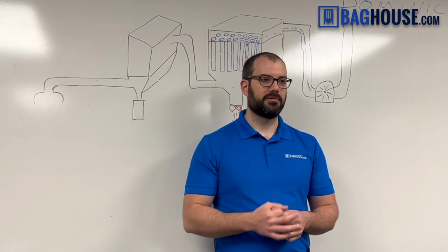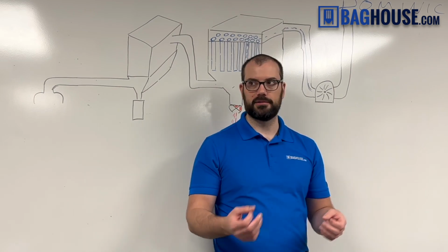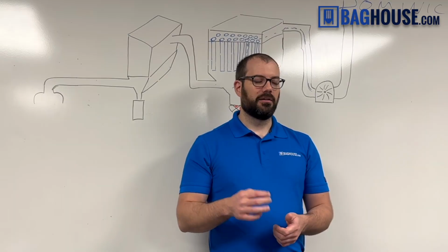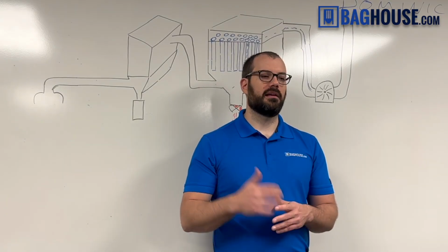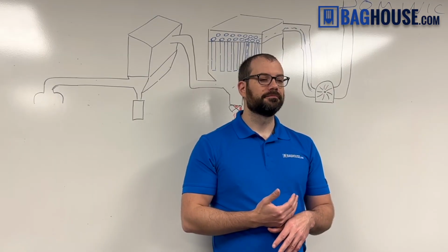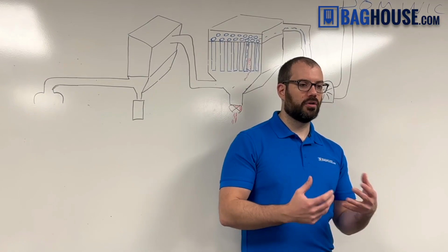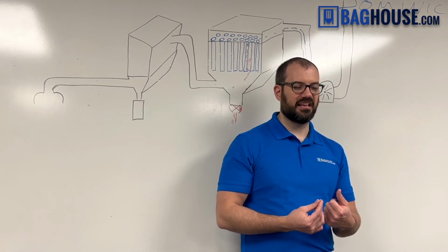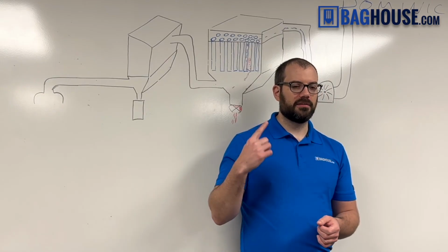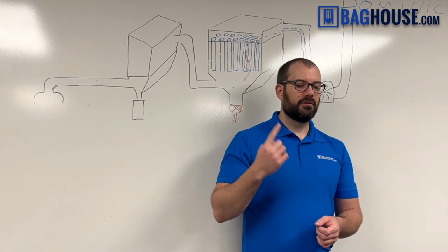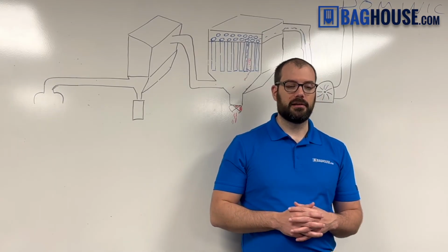It means particles, dust that's made out of metals, smoke particles, a physical thing. The gases that go through are something else that has to be done differently, right? And here you have dust with normal air, but also you have gases like chlorine that get injected, okay? So we have to think of that because the chlorine reacts with different things. So we have to think about that with the kind of material we select, okay?